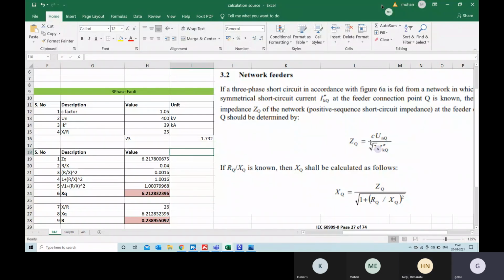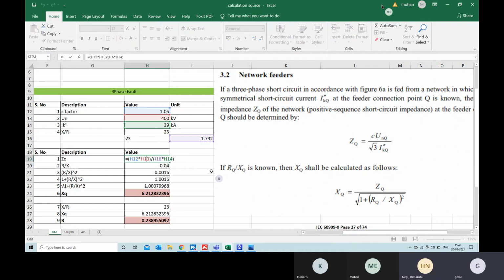ZQ is equal to C factor into 400, times 1.05 into 400, divided by root 3 into 39 kilo amps. So that's what I've used, and we got the value as 6.21.